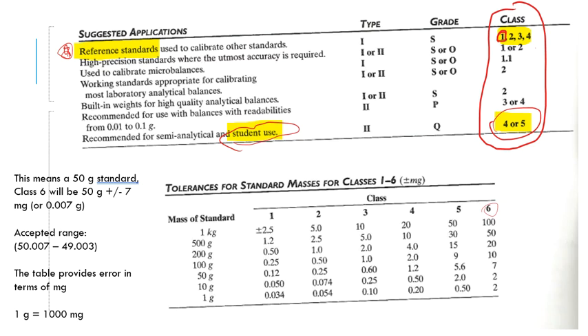Now, down here at the bottom, you're going to see something that we call tolerance. So the tolerance for the standardized calibration weight sets basically means error. Okay, how off would they be? So for instance, I can do a calibration set and class 1 is supposed to be the best. So that means when I put that calibration weight onto the balance, I should get that mass. That's how it's made. It is certified. But I know there's wiggle room. I know there's slight room for error.